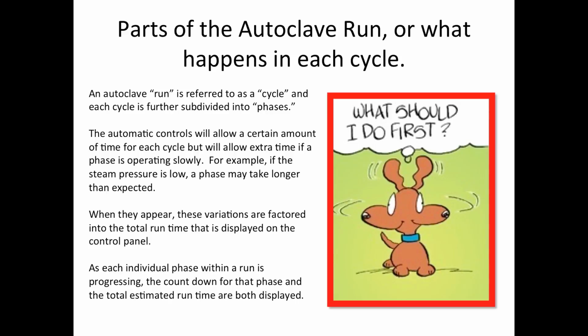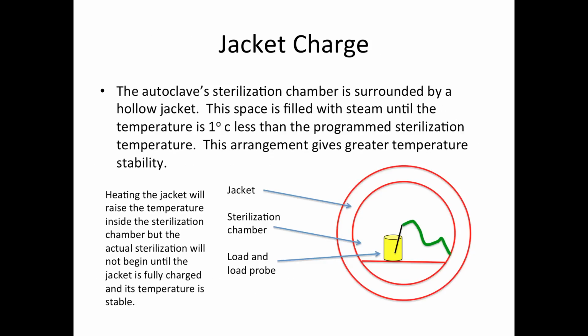The autoclave controls will allow a certain amount of time for each cycle, but will also allow extra time if a phase is operating slowly. So if the steam pressure is low, a phase might take a little longer than expected. Now, when these variations appear, they are factored into the total runtime that is displayed on the panel. As each individual phase within a run is progressing, the countdown for both that phase and the total estimated runtime will be displayed on the screen.